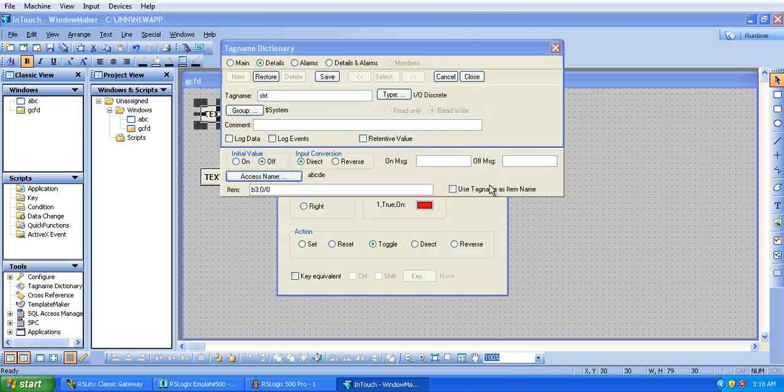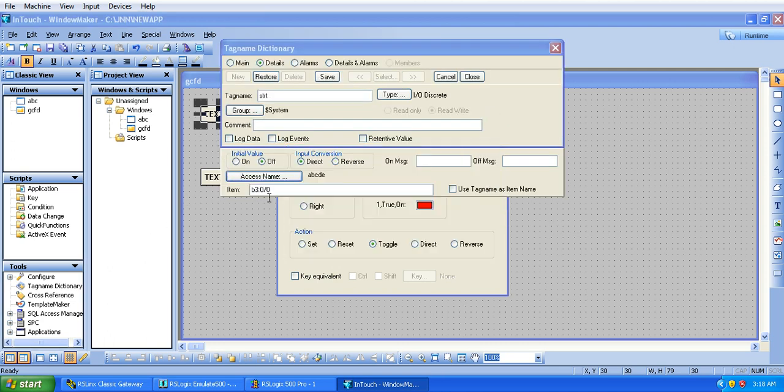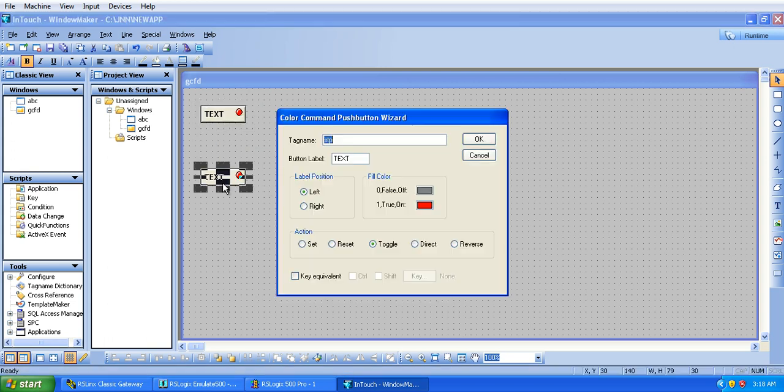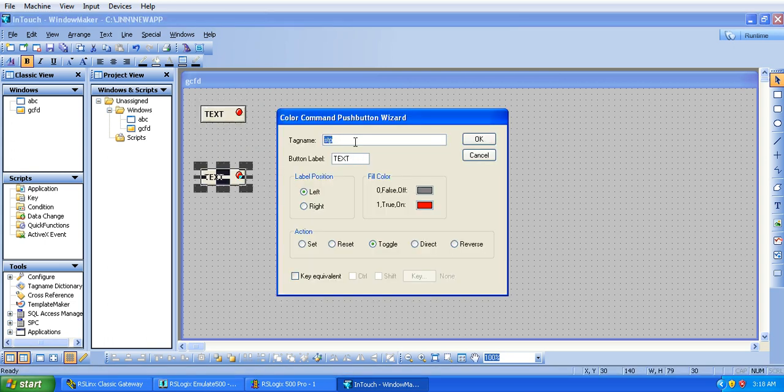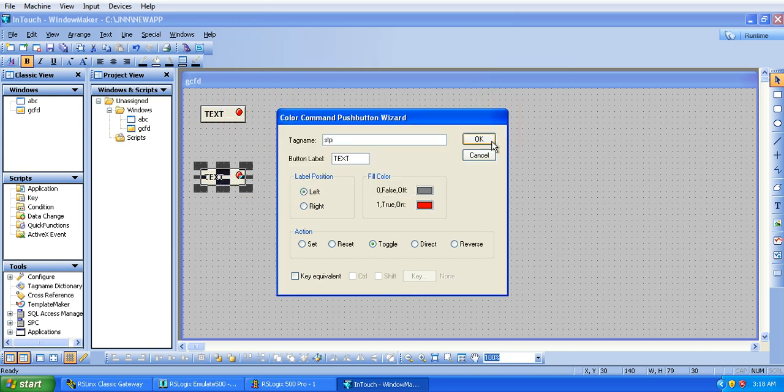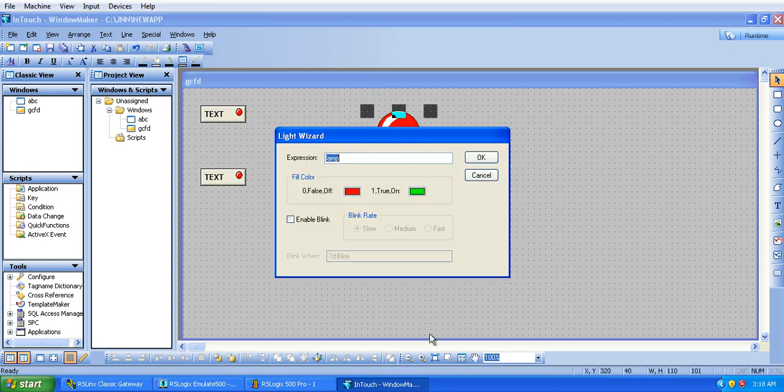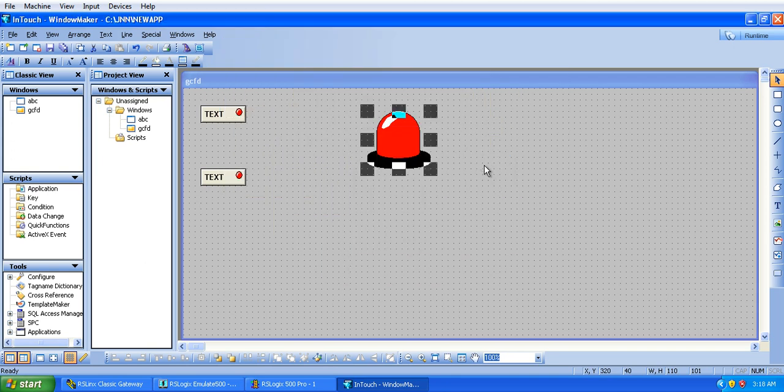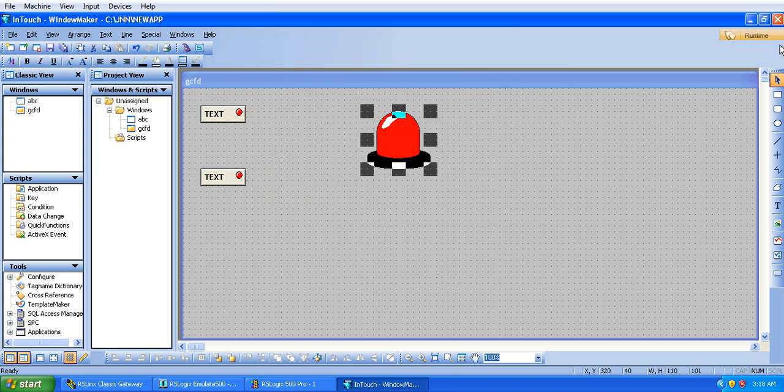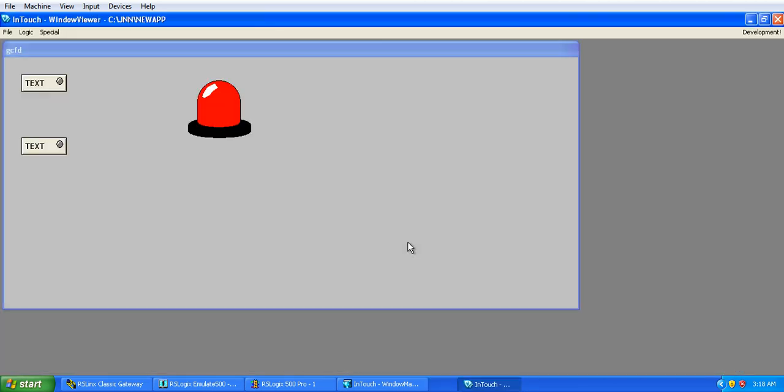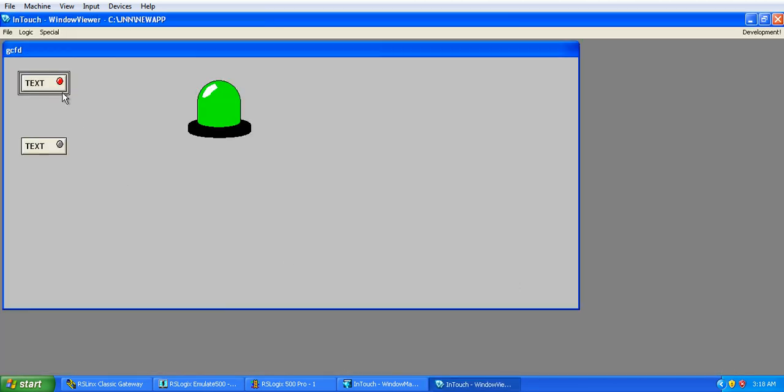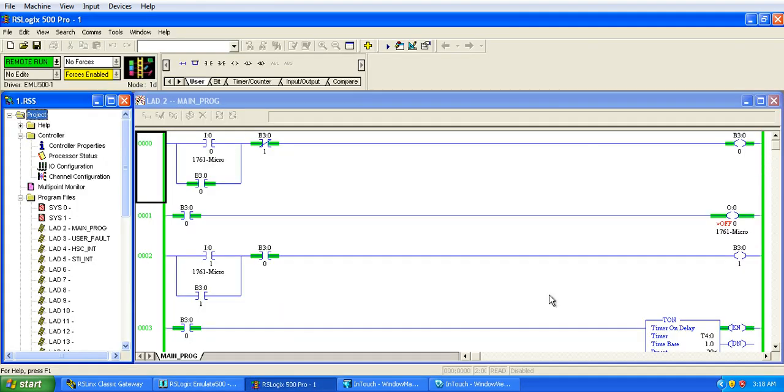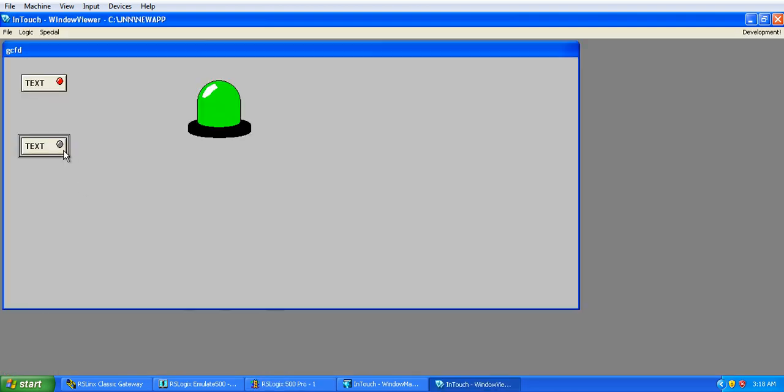And the address for the start switch is B3:0/0, and for the other stop button, the address is B3:0/1, and for the lamp the output address is O:0/0. Now run this program, here see that will also switch on here, and if I will stop button it will switch off this output.